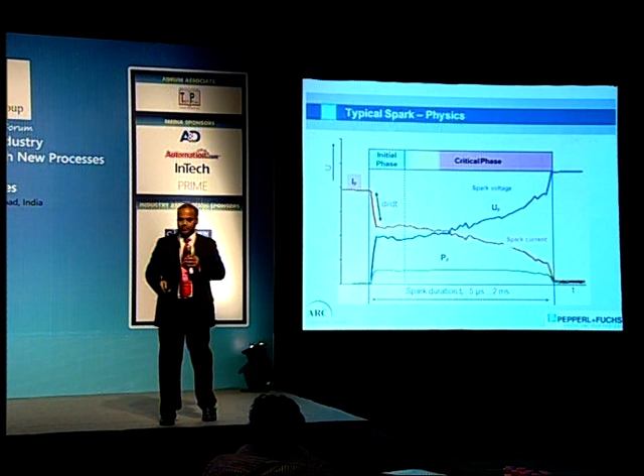In the normal intrinsic safe approach, whether there is a fault or no fault, the power supply always limits the power. In the dynamic way, we leave the power untouched, and when there's a problem in the field, such as a cable break or short circuit, it gets detected within microseconds.